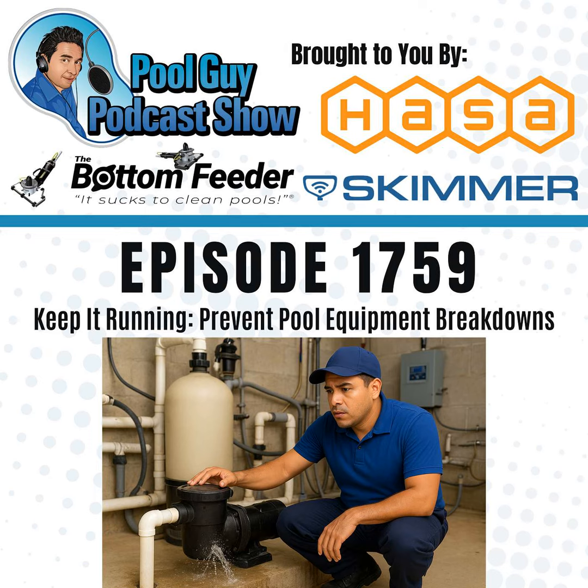So again, if you do have the bearings redone, it's not something that you can guarantee the customer it won't happen again. But I've had pretty good success with that. And I've had them last 2 or 3 years longer being rebuilt. And they call that rebuilding the motor, but it's just basically changing the bearings. And I find that that may be a solution in some cases, and you don't have to replace the motor.